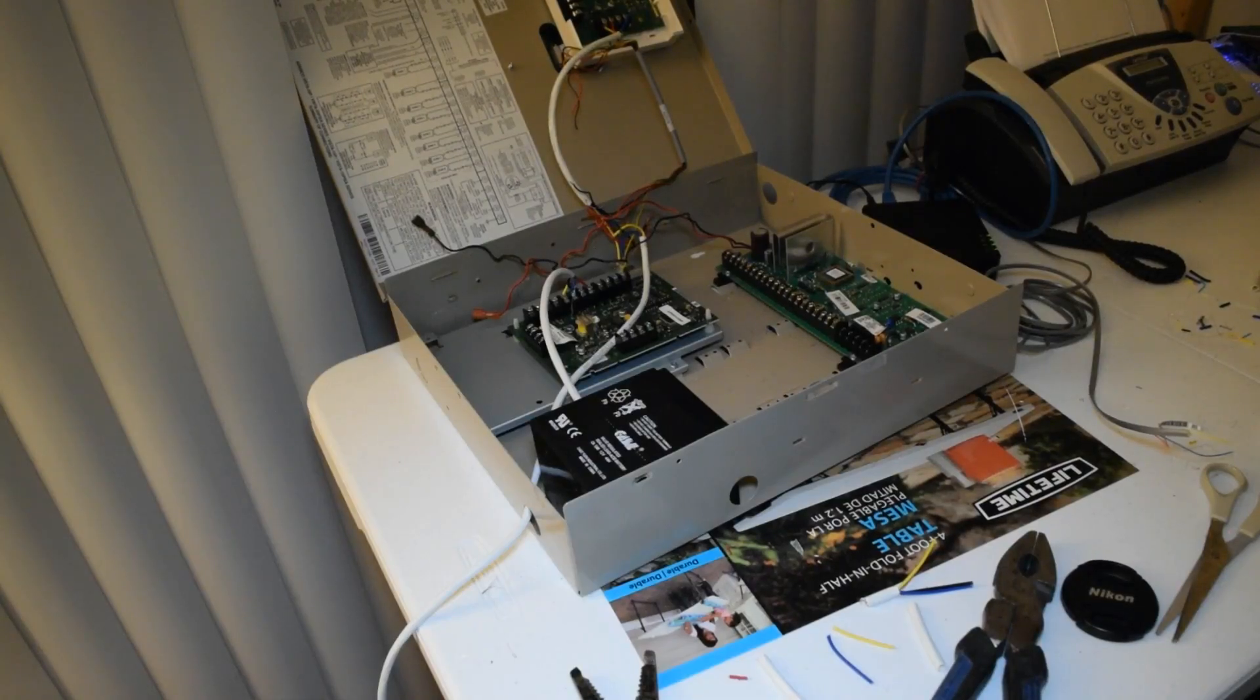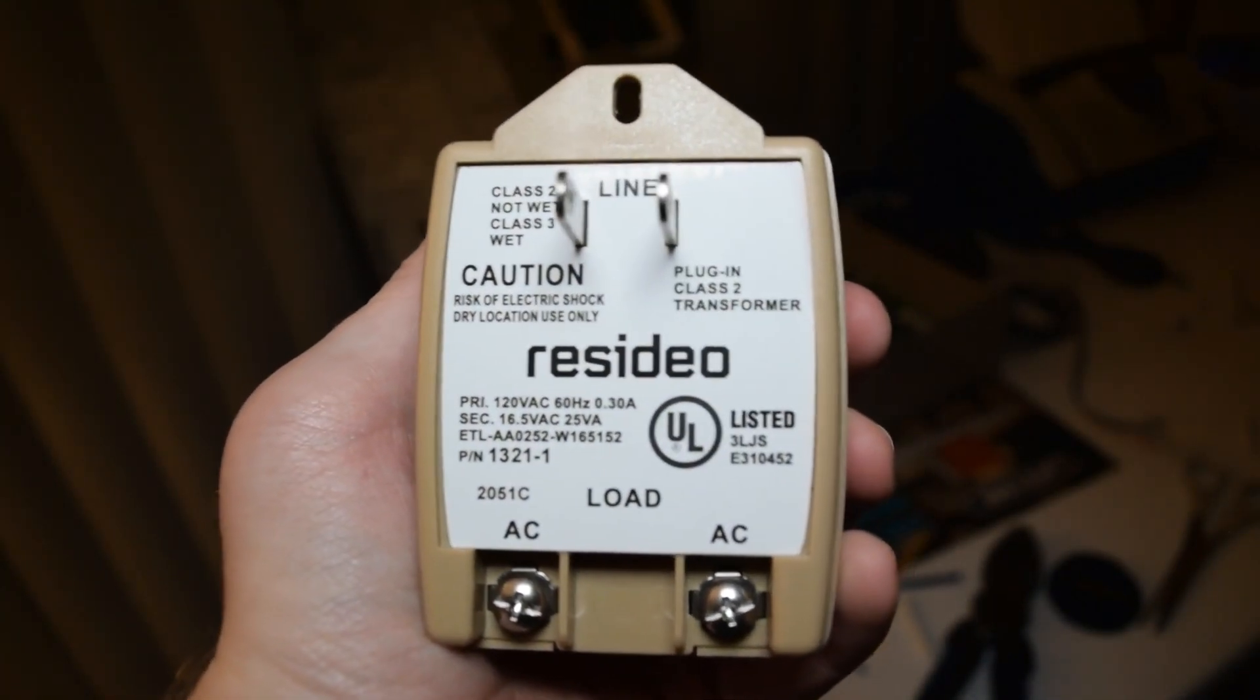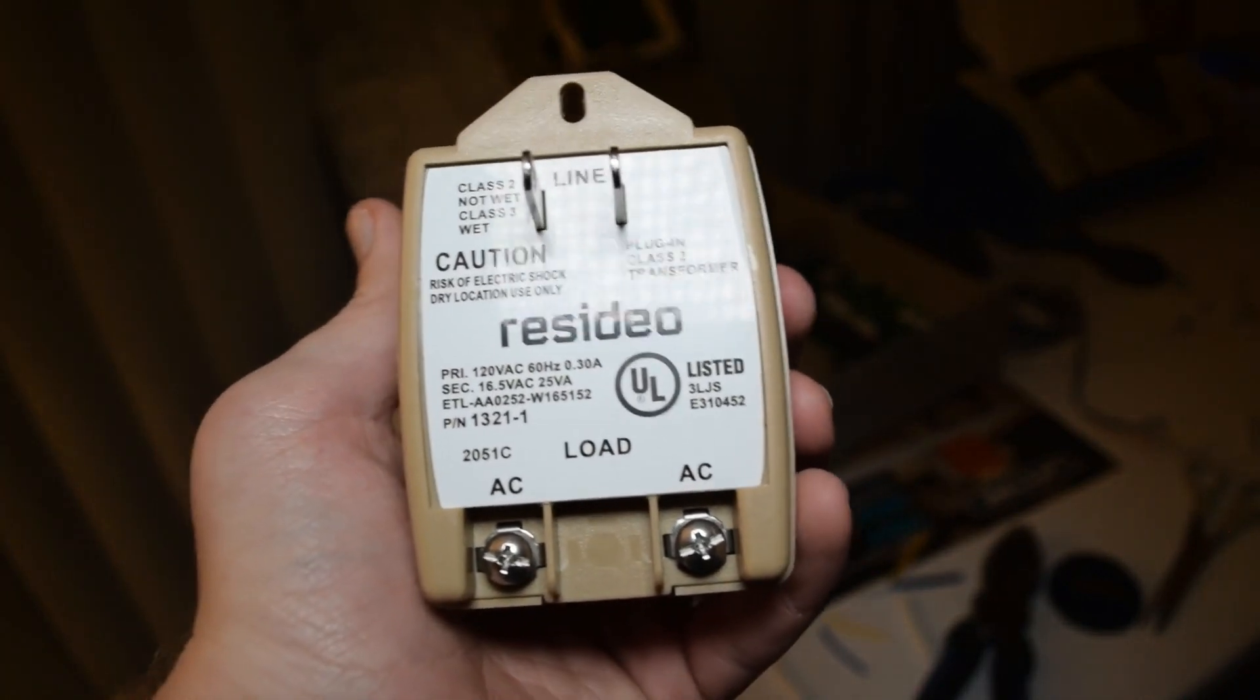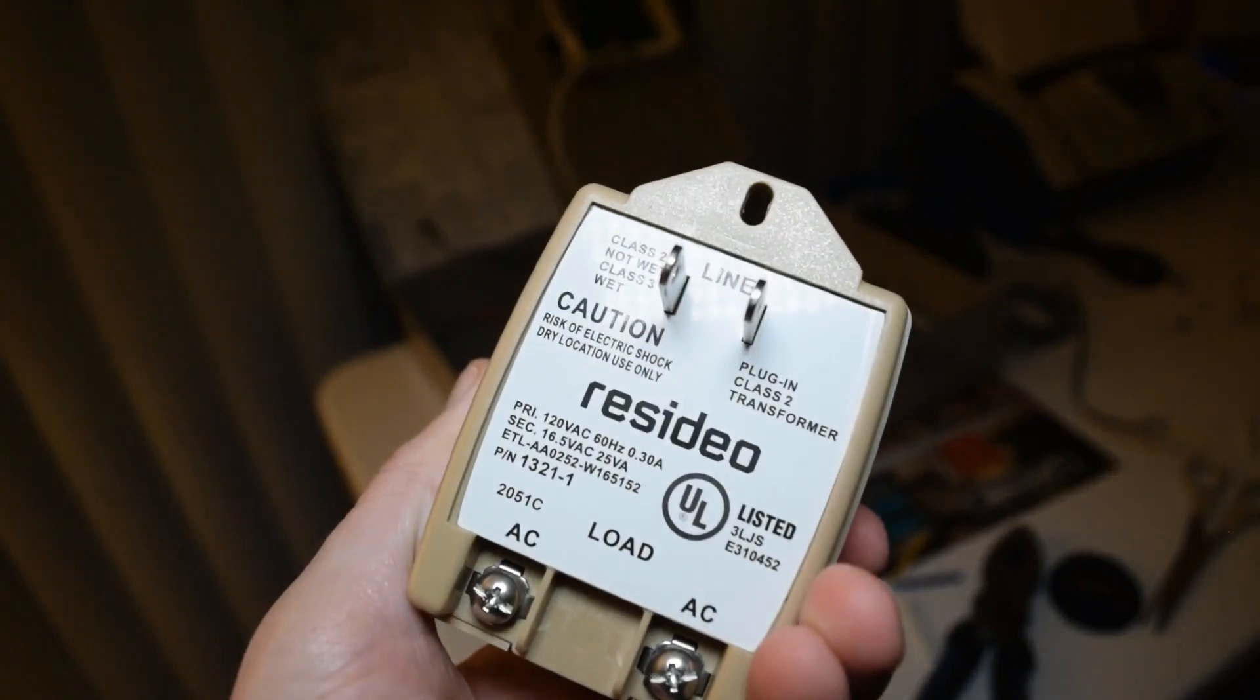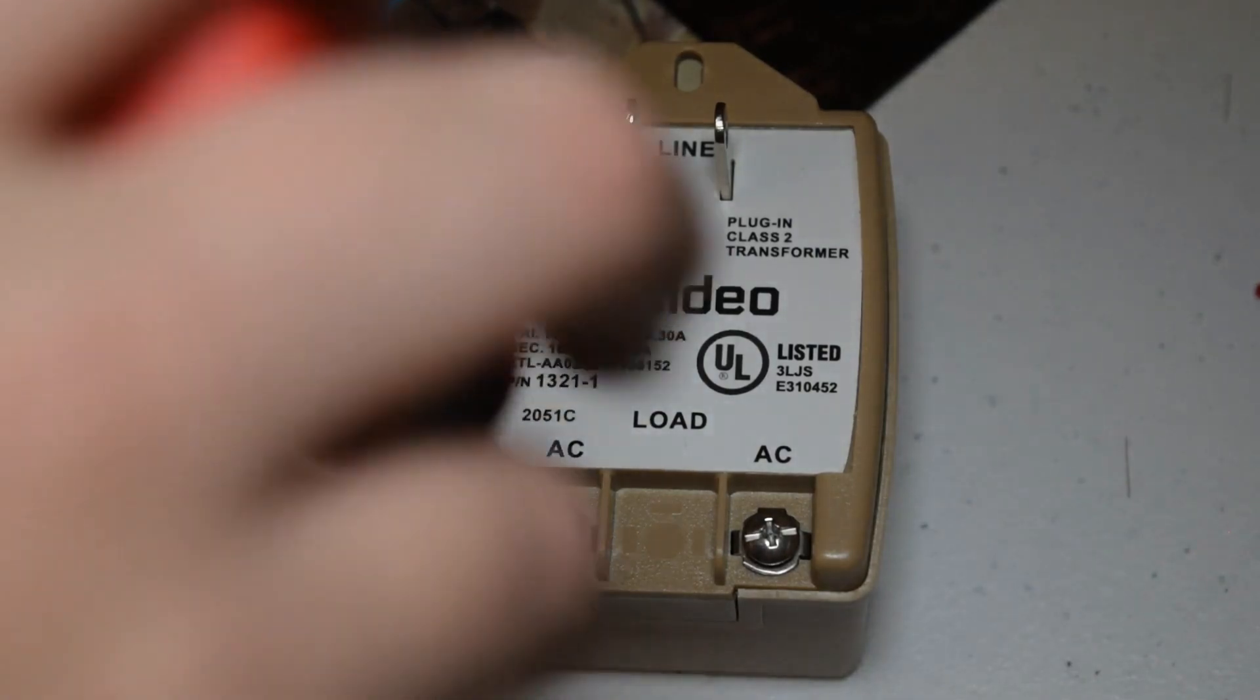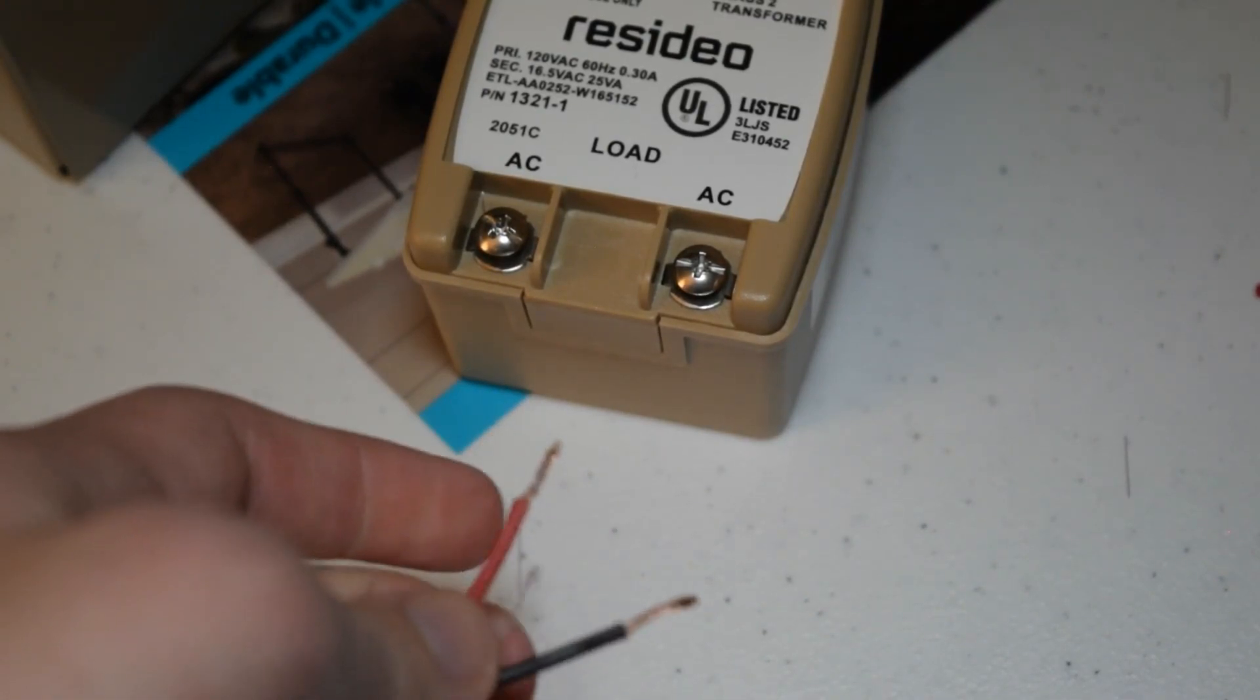The next thing that you'll need is the transformer that your security panel should have come with. This is what it looks like. This is the main transformer for the panel. It converts the wall voltage like 120 volts and steps it down to it looks like 16.5 volts. So hence why it's also such a big transformer. So now we're going to take the two wires that we just stripped and they're going to go in these two terminals on the transformer. First things first, just make sure the terminal screws are loose so you can get the wire in there smoothly. And it does not matter which wire goes in what terminal. It's AC, so polarity does not matter.